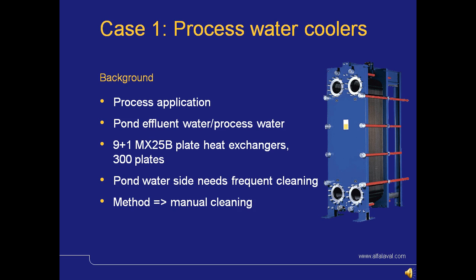The first case is about a customer within a process application. The customer uses pond effluent water to cool its own process water. The setup of the heat exchangers is 9 identical MX25B plate heat exchangers with 300 plates. They are connected in parallel, and on top of this the customer has 1 extra heat exchanger which is used while one of the other 9 is cleaned. These are fairly big heat exchangers, about 2.5 meters height and 1.5 meters width. So cleaning them is a bit of a challenge.